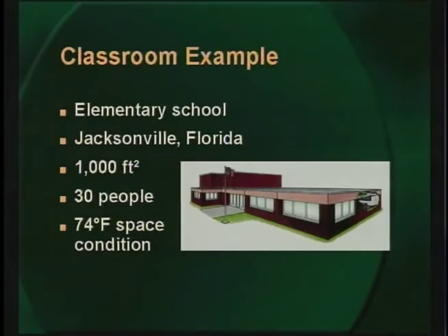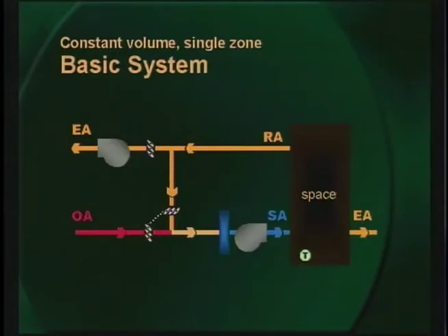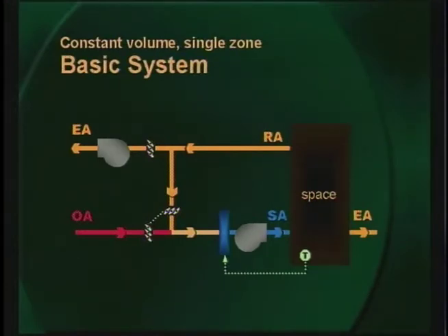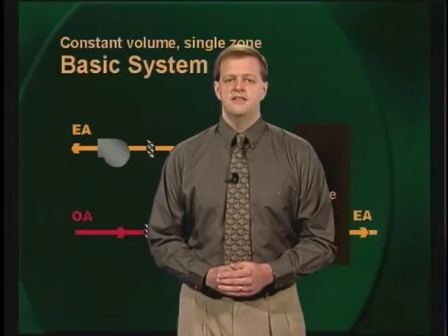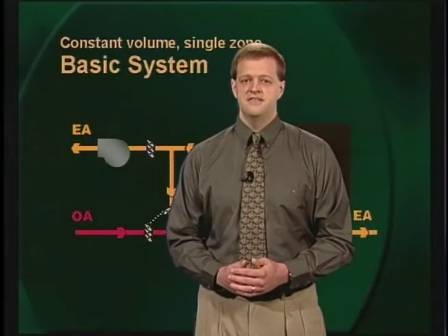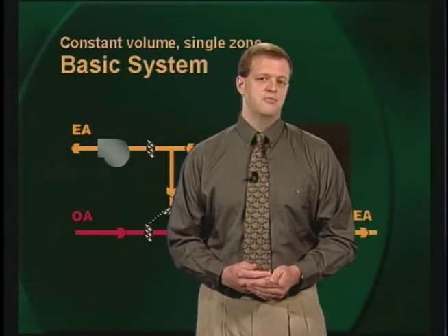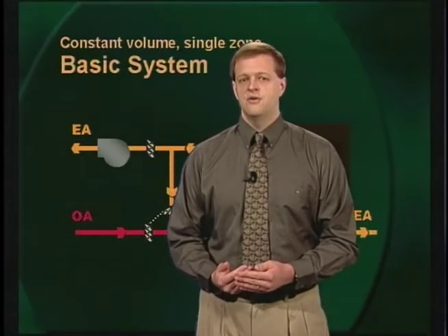This 1,000 square foot classroom contains 30 people and is designed to maintain a space condition of 74 degree dry bulb. Here's a schematic of the basic single zone constant volume system that serves this space. The thermostat senses the dry bulb temperature in the space and compares it to a set point. The capacity of the cooling coil is modulated to adjust the supply air temperature until the sensible capacity of the coil matches the sensible load in the space, maintaining space dry bulb temperature at the set point. A colder coil surface results in more moisture condensing on the coil and, in turn, a higher coil latent capacity.